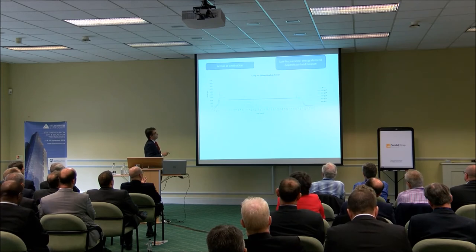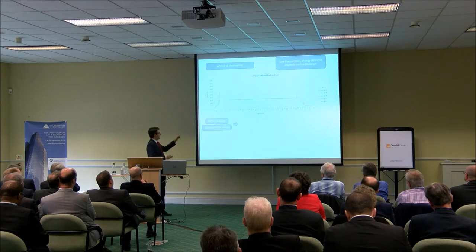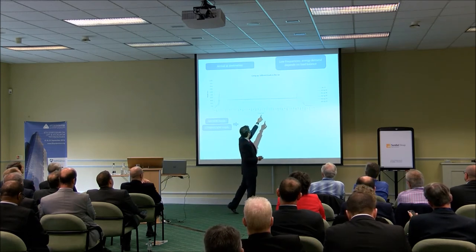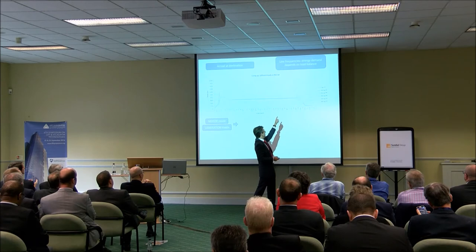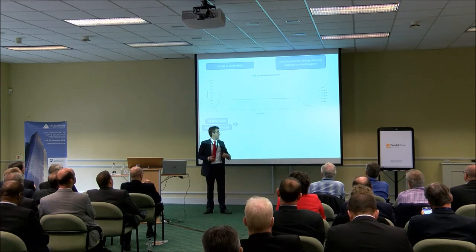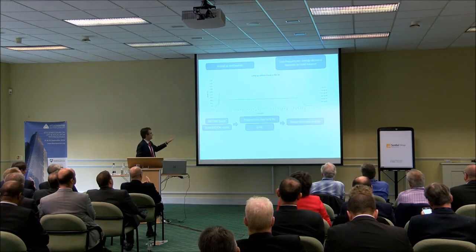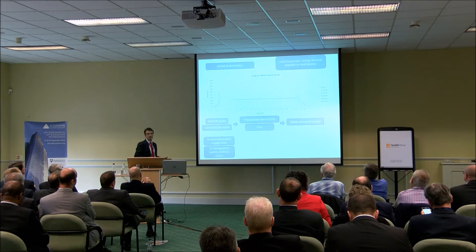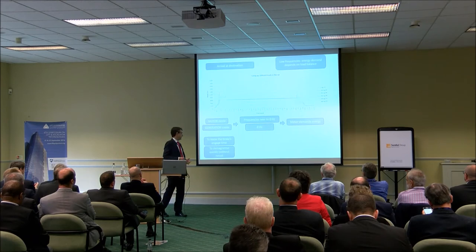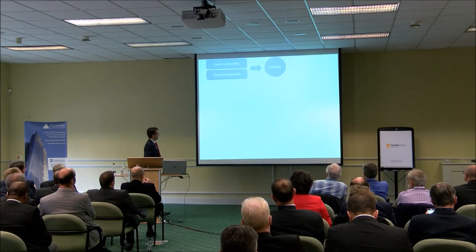This is the last stage of the journey — low frequencies. After traveling, you can see a horizontal generation mode. We are generating energy, but at the moment we reach speeds close to zero hertz, the lift starts to consume energy. This happens always, regardless of the load in the car. So we suggest knowing the proper brake engagement time and demagnetizing the motor as quickly as possible without producing noise to achieve energy savings.